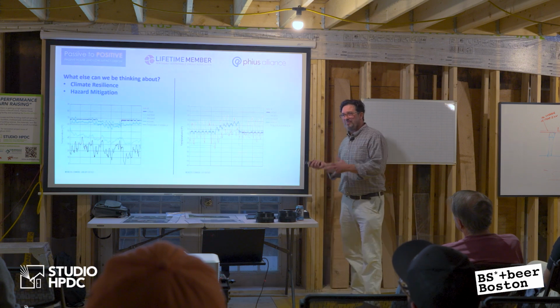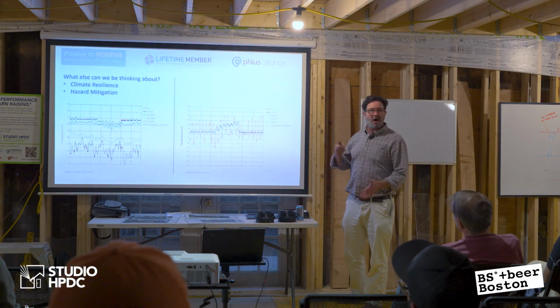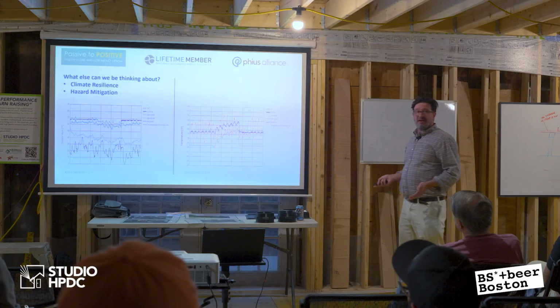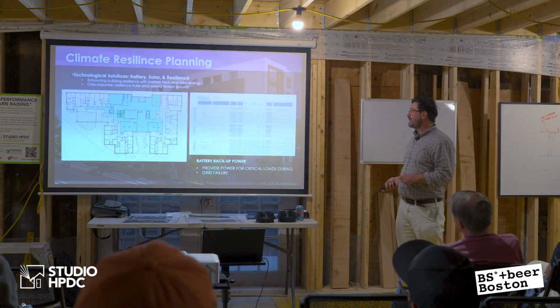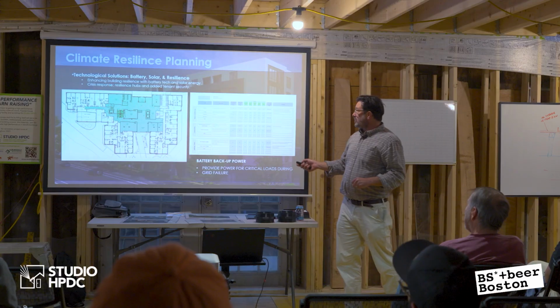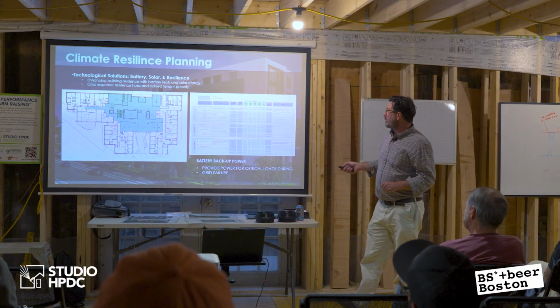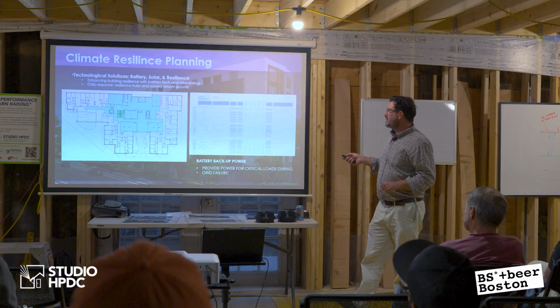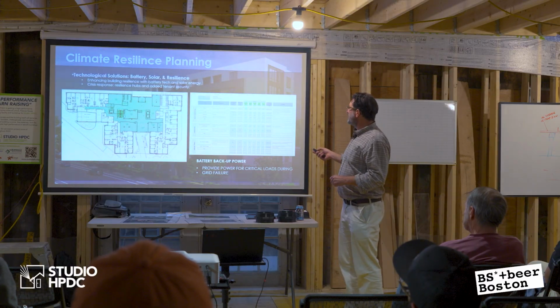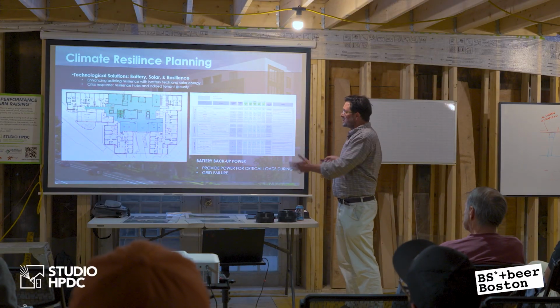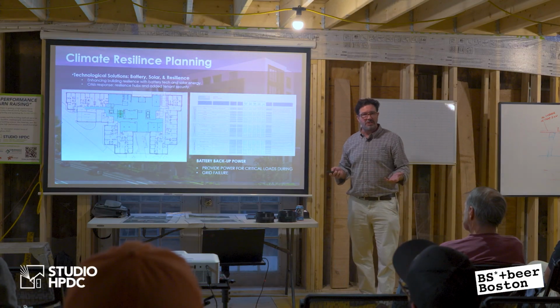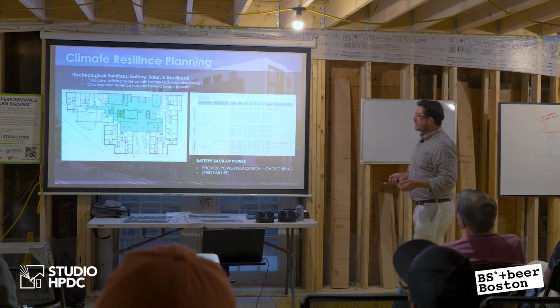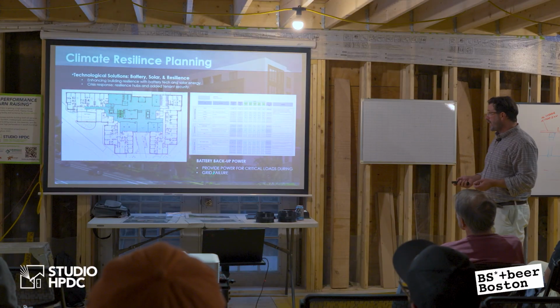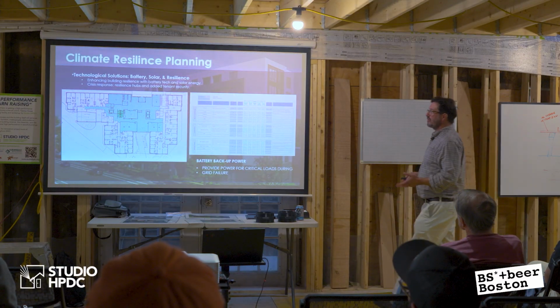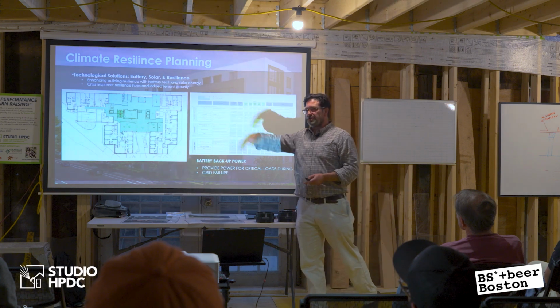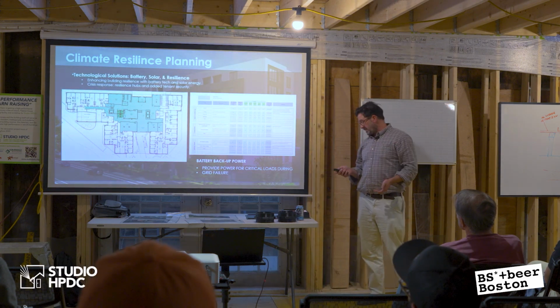So we can size our battery system to account for operating over an extended or indefinite period if we reduce our loads. So we can define a critical load zone, and we do an intake form where we say, okay, this thing, is it a critical load? Which zone is it in? And we get an owner's sense of how the building needs to function in case of emergency. That's another thing we could entertain here. And then you provide backup power based on that. How much can you afford to keep as a critical load zone to drive resiliency, to extend your resilience?